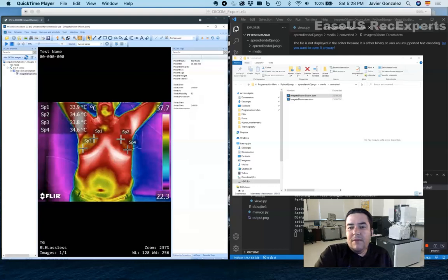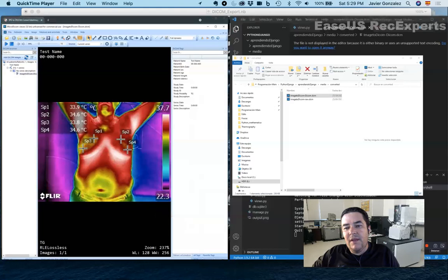I'm aware there might be other ways around this. Like I mentioned, you can plug in the minimum temperature and the highest temperature before generating the DICOM file, and then calibrate the whole JPEG file into a bunch of temperatures.